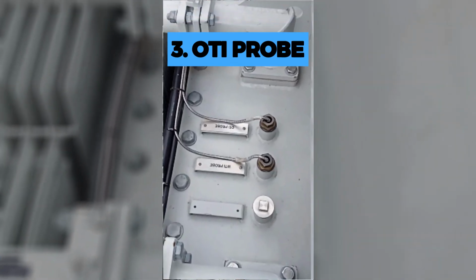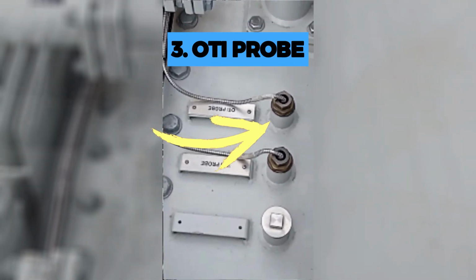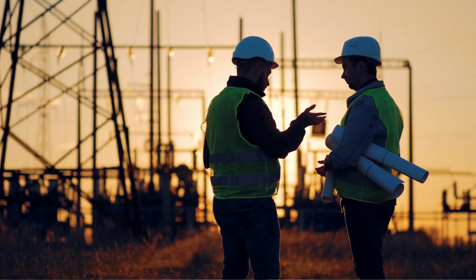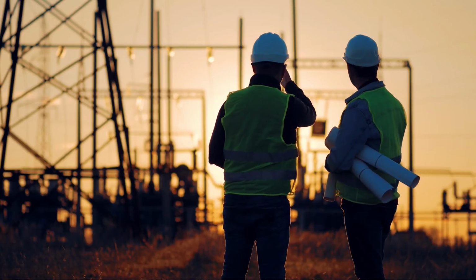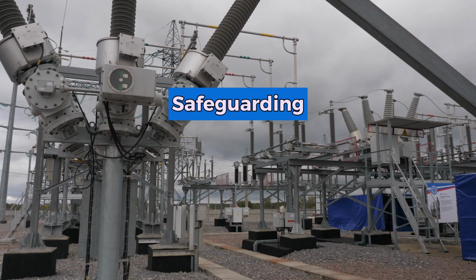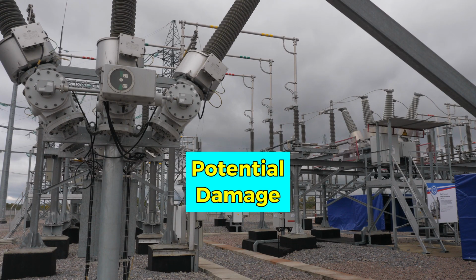Moving on to the OTI probe, which stands for oil temperature indicator. This device constantly measures the temperature of the transformer oil. It's vital in alerting us to any abnormal temperature rise, safeguarding the transformer from potential damage.